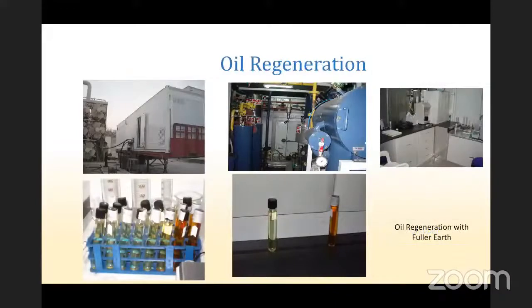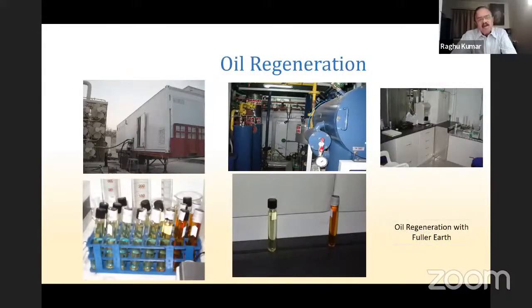This is an example of an oil regeneration. Oil regeneration can be achieved at almost half the cost of new oil. The equipment comes in a container, and this container has two compartments. One compartment is where the oil reclamation process takes place, and the second one is a laboratory setup where the oil can be continuously tested. This is a two-part process. One is oil filtering, and the second is that it is passed through columns of fuller earth. And this is what removes the acidity, sludge, and stuff like that.